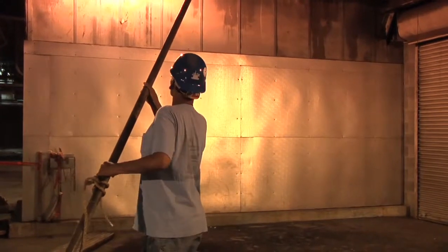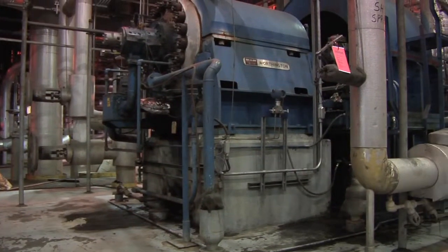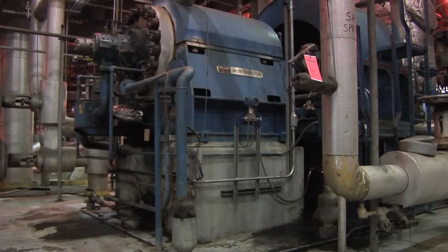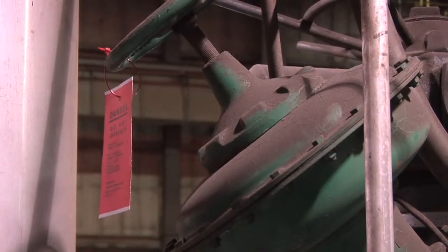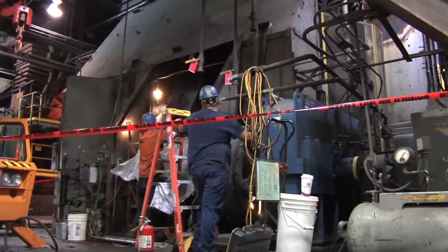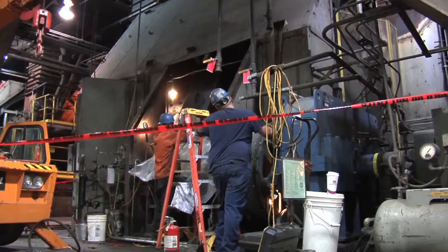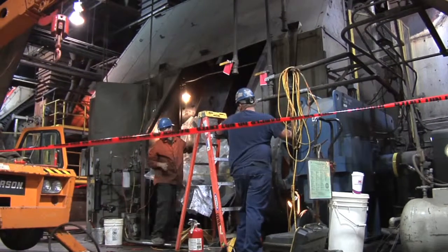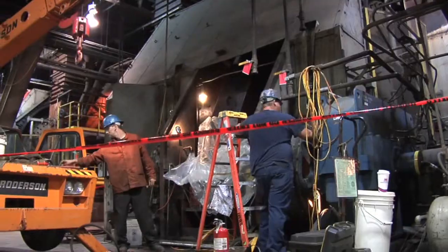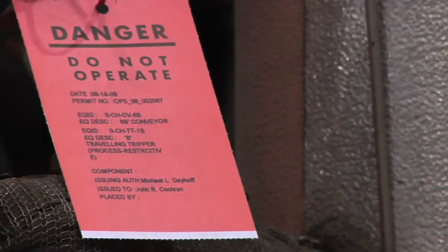This procedure shall be used to ensure that the machine or equipment is stopped, isolated from all potentially hazardous energy sources, and tagged out before employees or contractors perform any servicing or maintenance. Clearance tags reference a hard copy permit that is kept in the control room. Red tag permits are used when equipment must be isolated and energy free for repair or servicing by one or more work groups. A red tag permit shall be used when more than one work group works on equipment concurrently.